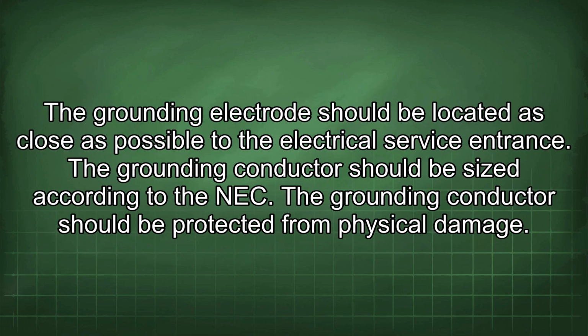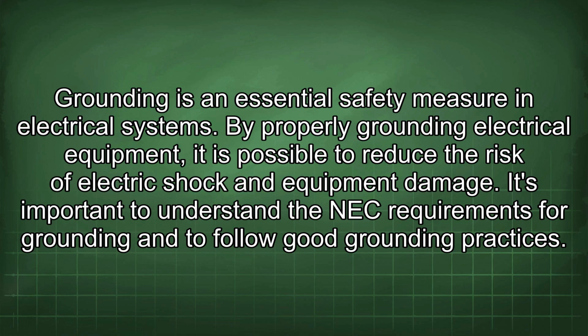The grounding electrode should be located as close as possible to the electrical service entrance. The grounding conductor should be sized according to the NEC. The grounding conductor should be protected from physical damage. Grounding is an essential safety measure in electrical systems. By properly grounding electrical equipment, it is possible to reduce the risk of electric shock and equipment damage. It's important to understand the NEC requirements for grounding and to follow good grounding practices.